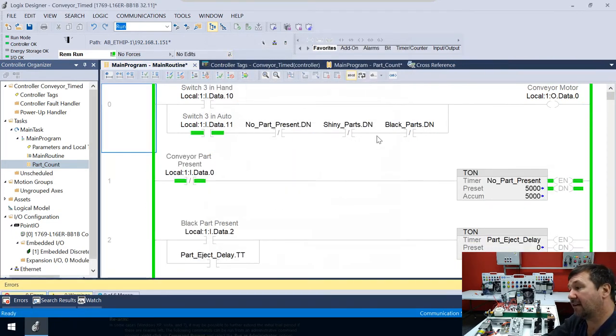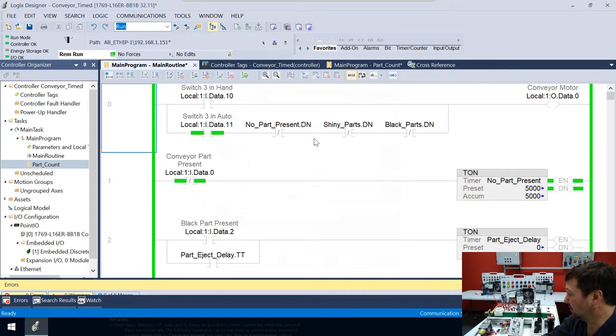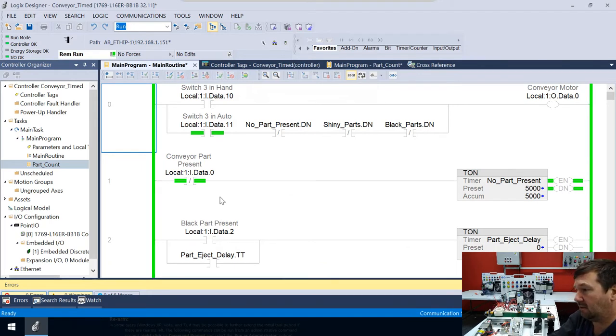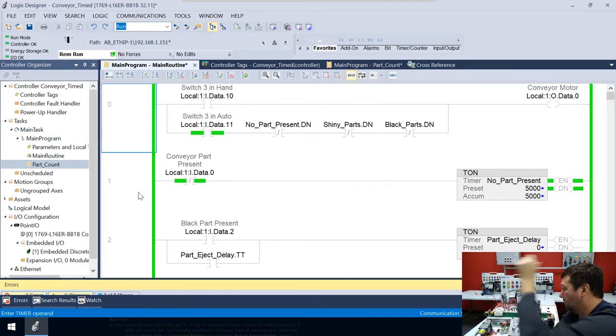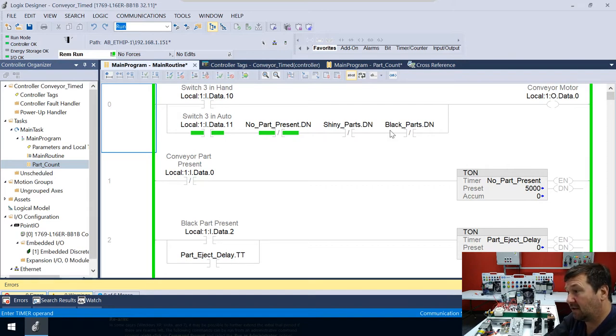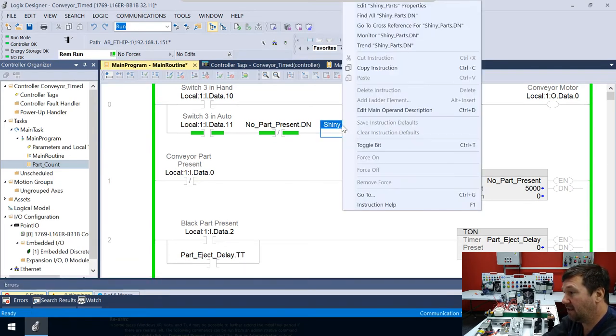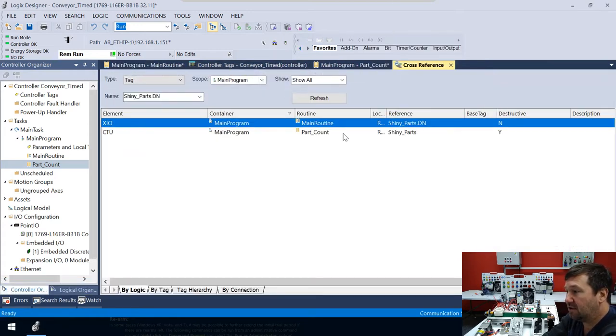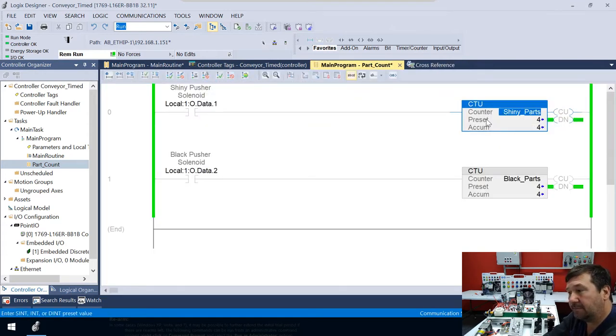And right away, we can already see we have three conditions now that are preventing our conveyor from running. So we know how to fix this one, no part present. We just got to drop a part in it, right? Because right below it, here is that timer. Five seconds and not seen a part. So I'm going to throw a part in there. But it's not going to go anywhere because we're stopping on these two. So let's go check them out. And let's use the cross-reference to find them again. So right-click and let's go to cross-reference. So now we see two locations and we see that this one is destructive. And there we are. Our counters are done.